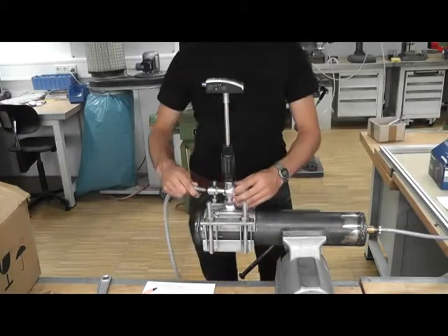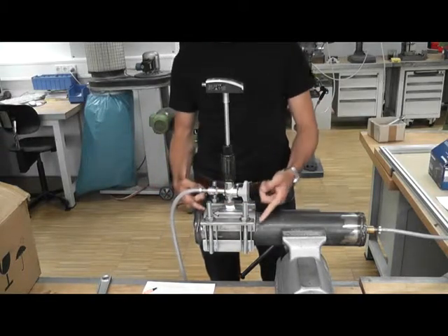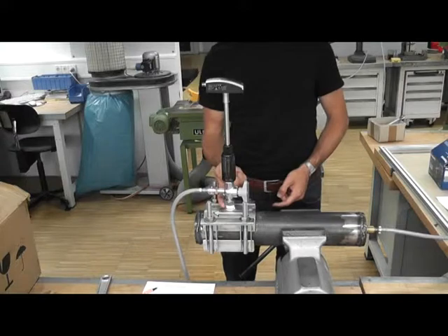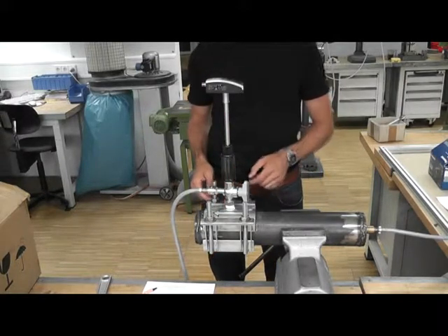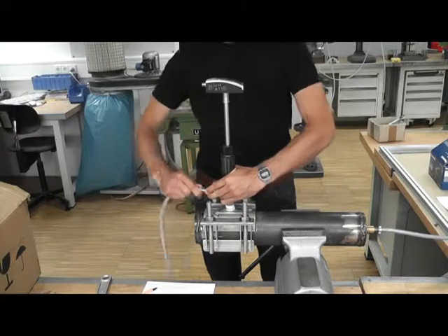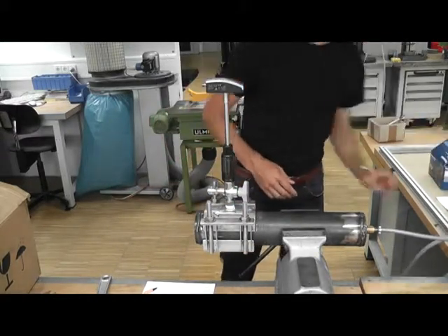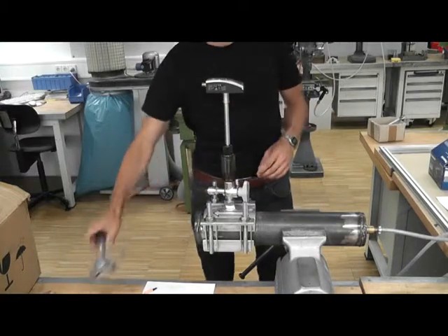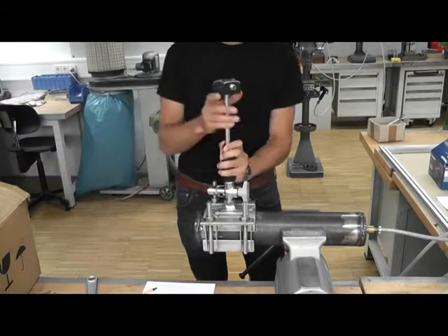Before you uninstall the transmitter, you should also prove if the tapping clamp fits leak-proof on the pipe. Therefore, mount the compressed air hose to the ball valve. If you hear no sound of compressed air, the tapping clamp fits leak-proof on the pipe. The last point is to uninstall the transmitter.